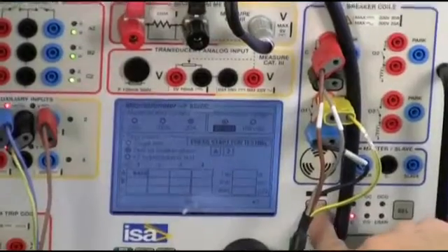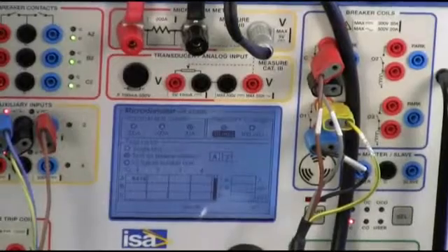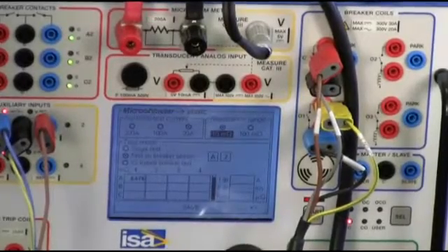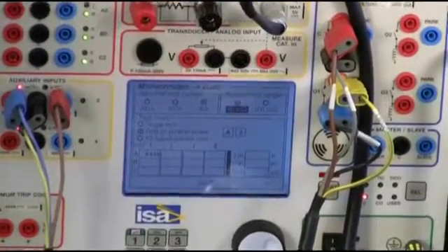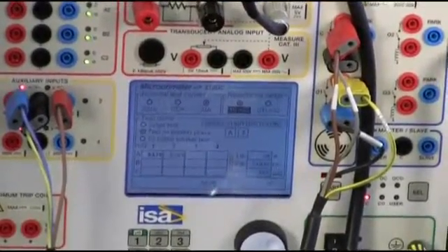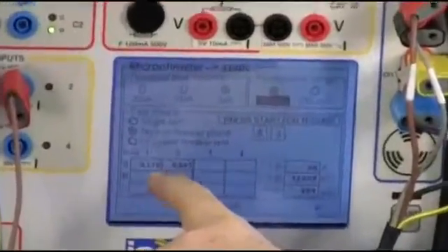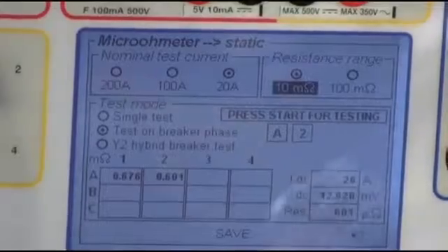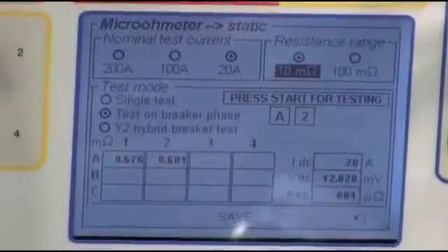Now, I press start. Again, my capacitor being charged. Okay? You see, 0601 instead of 0676. So, practically speaking, the measurement is the same, even if the test current is much less.